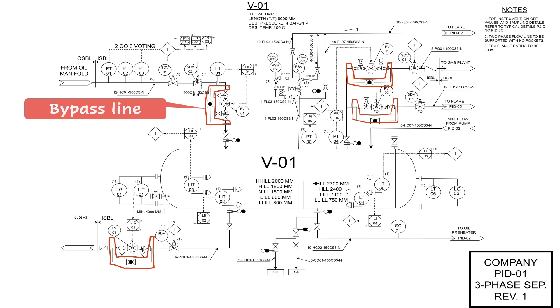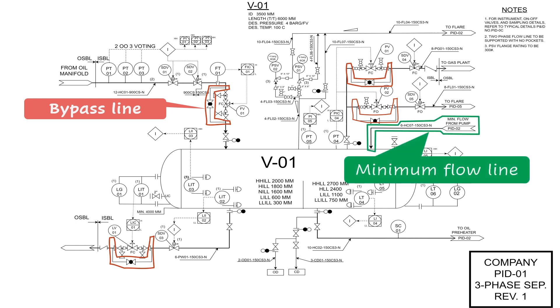Or in case of a pump, if the pump doesn't have a minimum flow through a control valve, but through a restriction orifice, the minimum flow line is not commonly shown on the PFDs, but it shall be shown on the P&IDs.